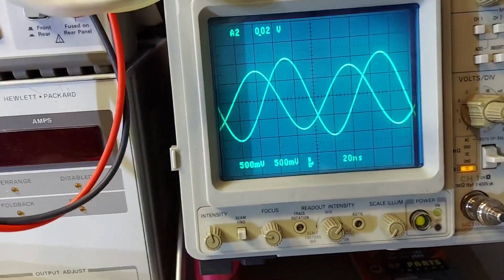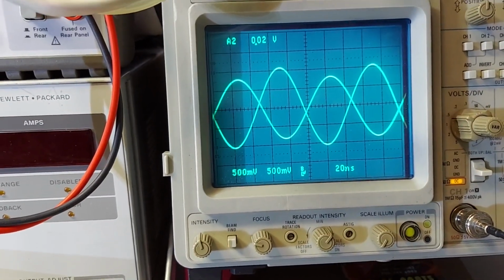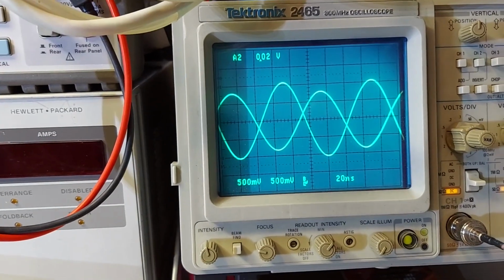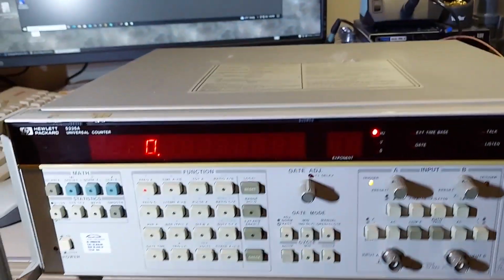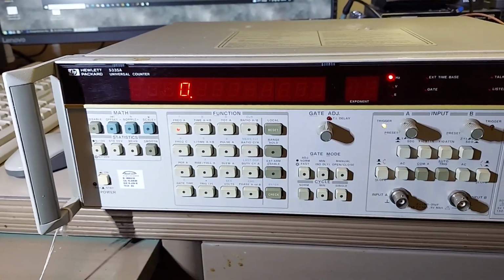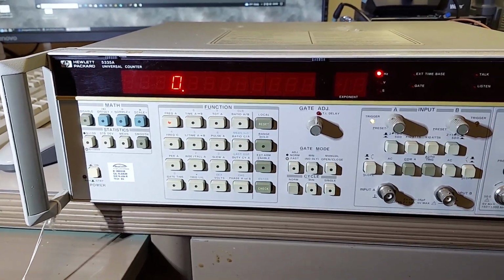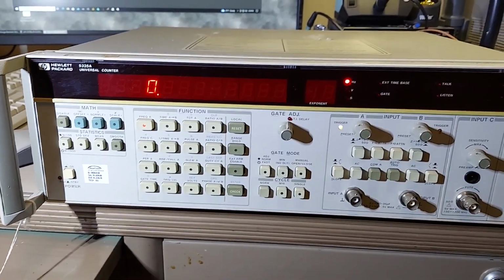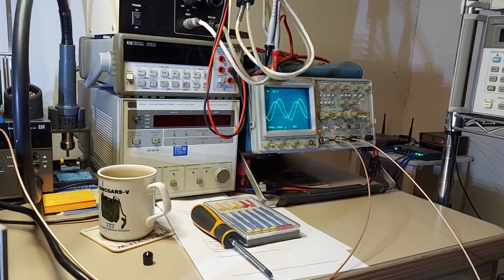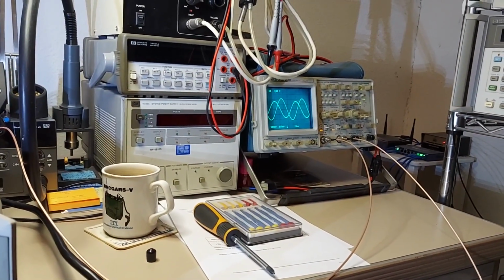What we're going to do, though, is adjust the time base, because it is running a little fast. According to the display, it's running about 70 millihertz low. So we're going to open this thing up, and we're going to adjust it until that trace stops moving.